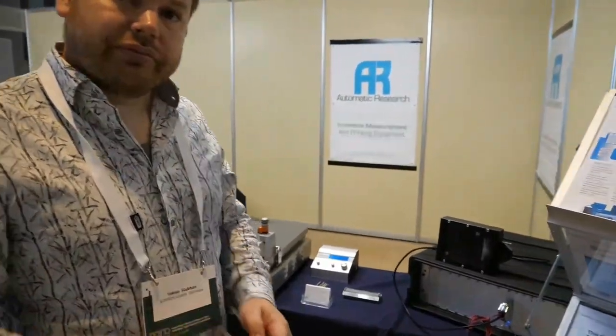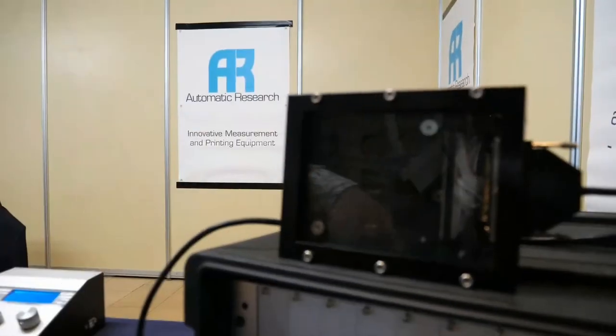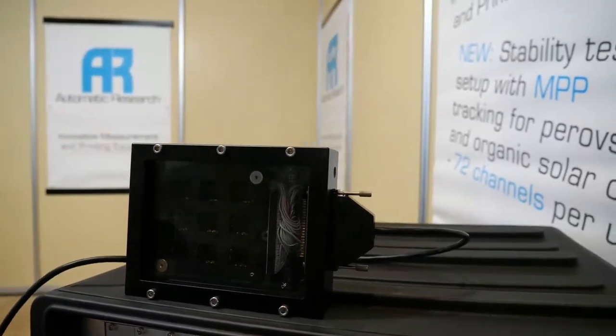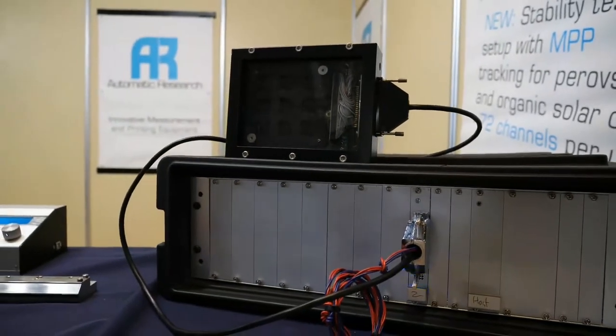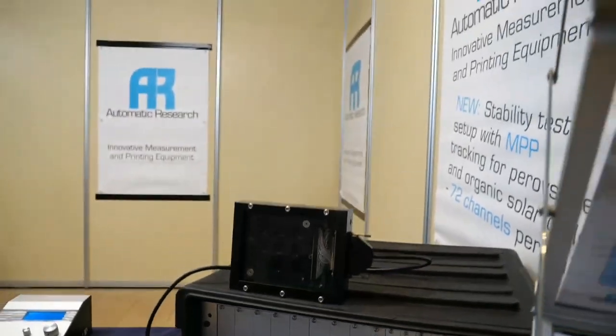Stability of solar cells. Yes. So all the cells, you can illuminate them here. You can put in like nine substrates at a time in one of these holders and all of them can be kept at their maximum power point individually. That's something that is very often needed for perovskite research. So a lot of people are researching perovskite right now.